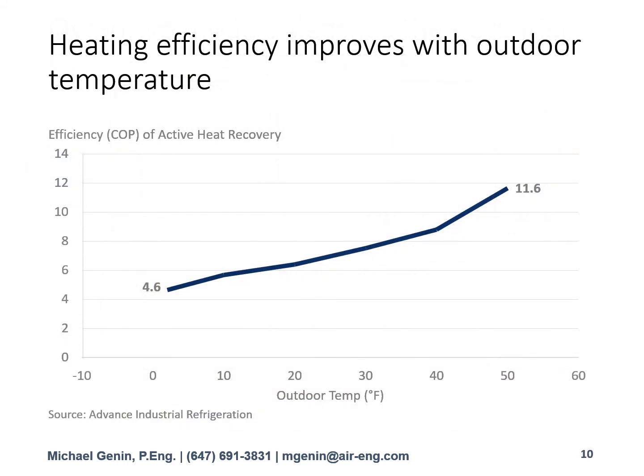So we've plotted outdoor air temperature against the efficiency COP for active heat recovery. And the efficiency varies greatly with the outdoor air temperature. Down to a design condition of -4 that we've been talking about, you can expect a COP of around 4. And on more mild days, when you approach 50 Fahrenheit, you can expect a COP of 12.